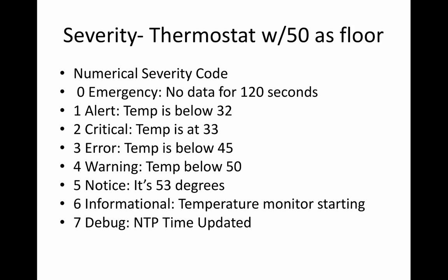So that's what it's basically used for. Like maybe a level 3 is we send an email. A level 2 is like a text message is generated. And a level 1 alarm is there's an automated call system that starts calling a phone tree of people because something's bad going on. And then 0 is also not so good.